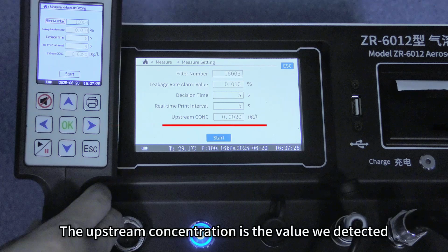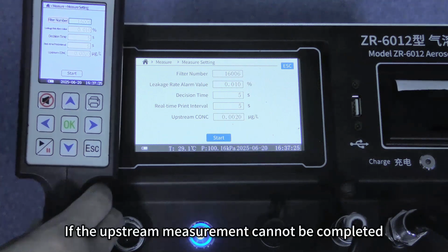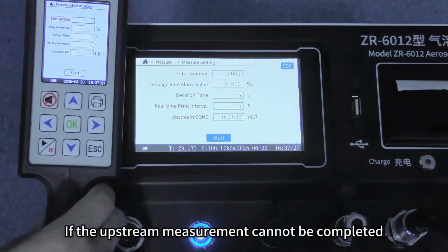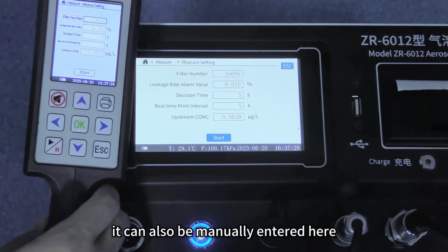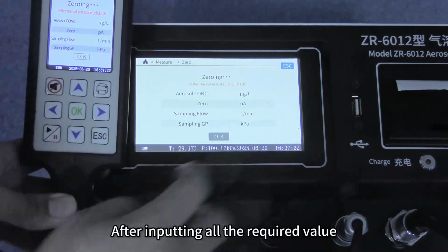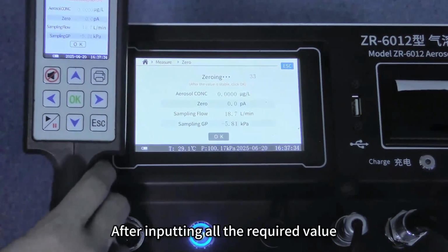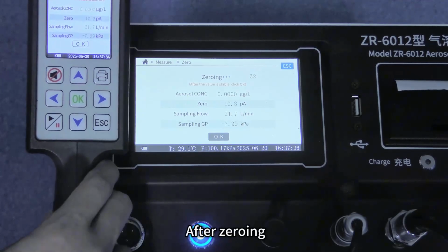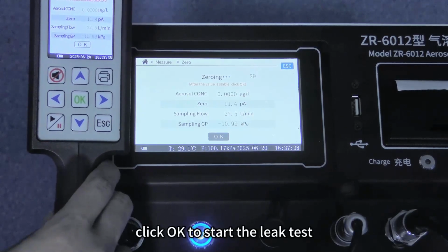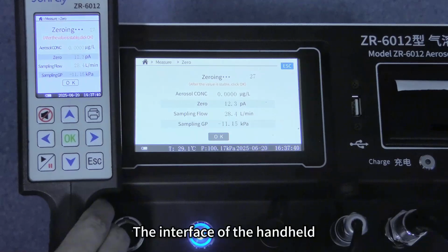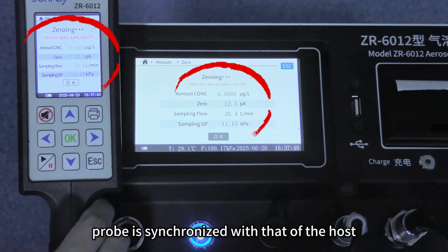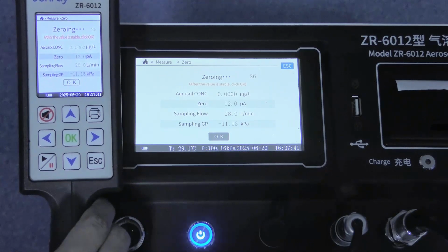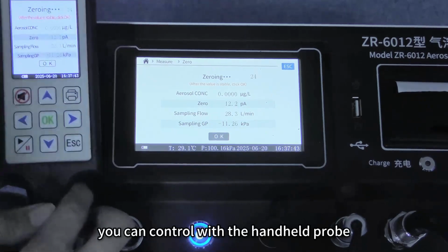The upstream concentration is the value we detected in the earlier process. If the upstream measurement cannot be completed, it can also be manually entered here. After inputting all the required values, you can click Start. After zeroing, click OK to start the leak test. The interface of the handheld probe is synchronized with that of the host. You can control with the handheld probe.